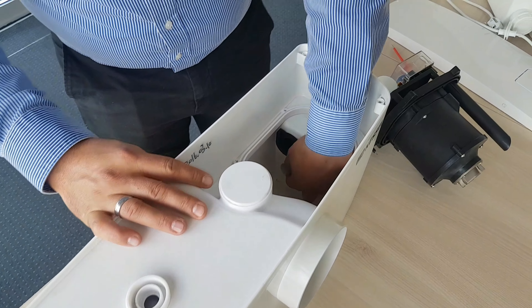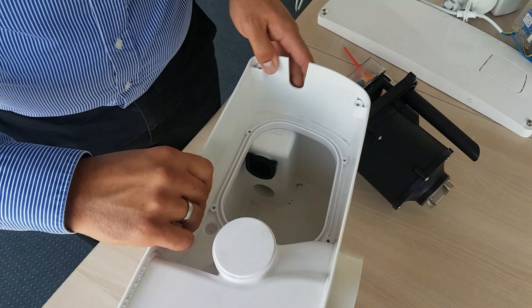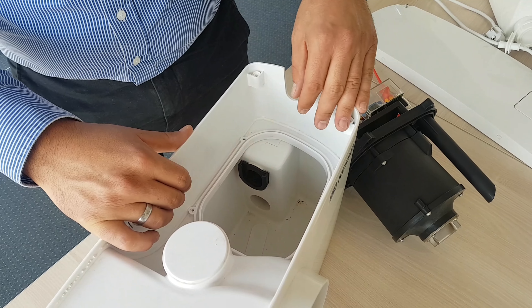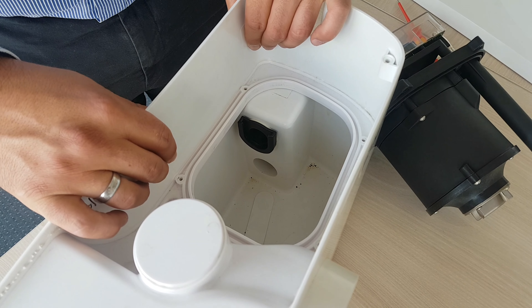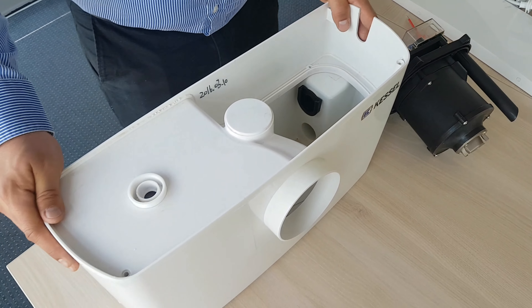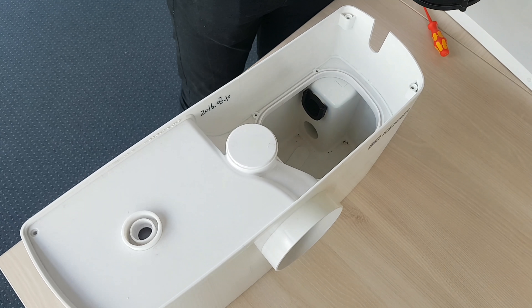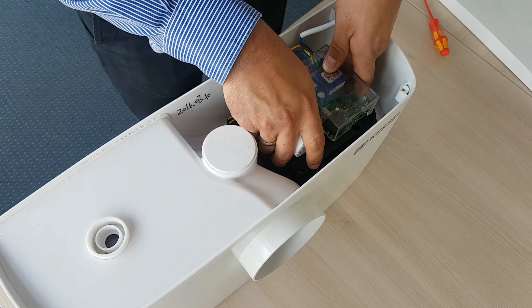The next thing to do would be to check the inside of the tank. You would have to take a hose and clean it with water. Also, don't forget to check the backflow preventer located here — it has a small rubber ball in it, and it also has to be cleaned, best with fresh water using a hose.